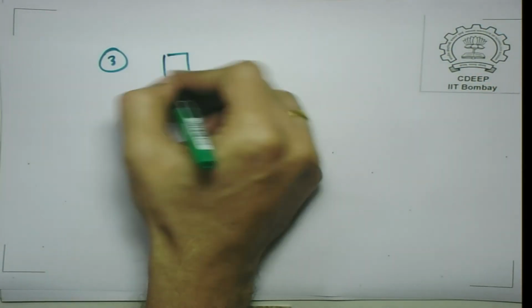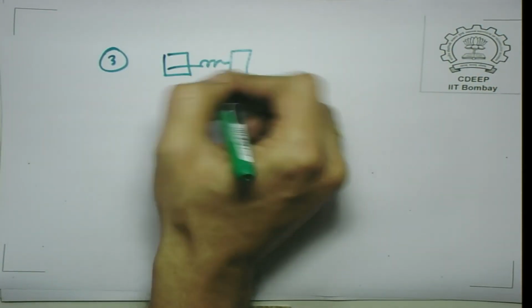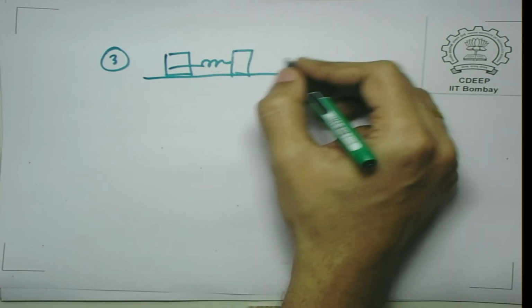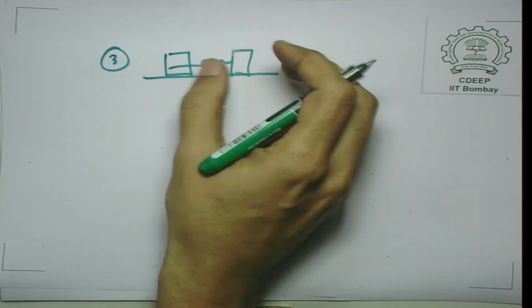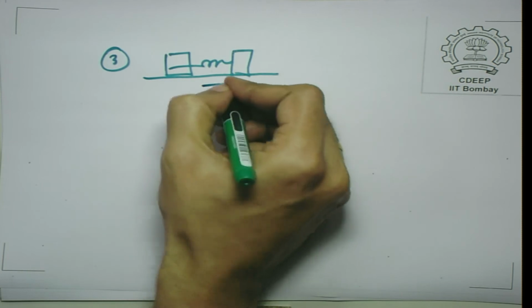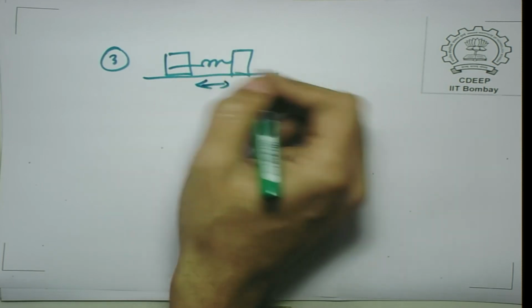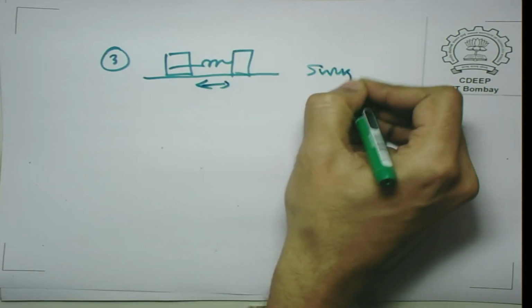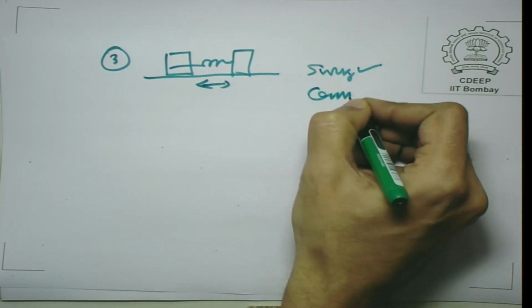If you have two masses connected to each other, then you have both common motion, which depends on the total load generation balance, and you also have swing, that is inter-machine oscillation. So swing is there and common motion is there.